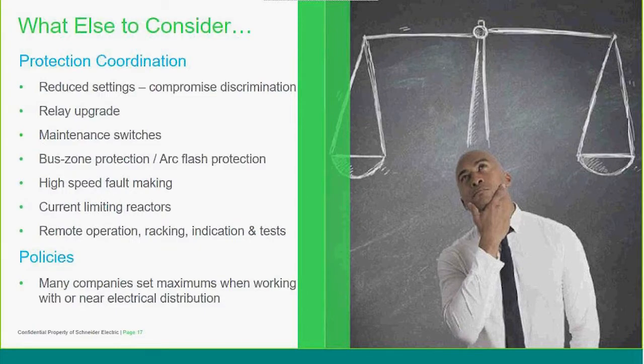As we said, protection coordination is a whole subject matter in itself, looking at discrimination and maybe compromising it. That's why it's very good, whilst you're having the protection study and the fault level assessment done, to simultaneously do the arc flash, because you might well be able to adjust protection settings to reduce incident energy levels without impacting your discrimination. It's a three-way triangle that are interlinked.